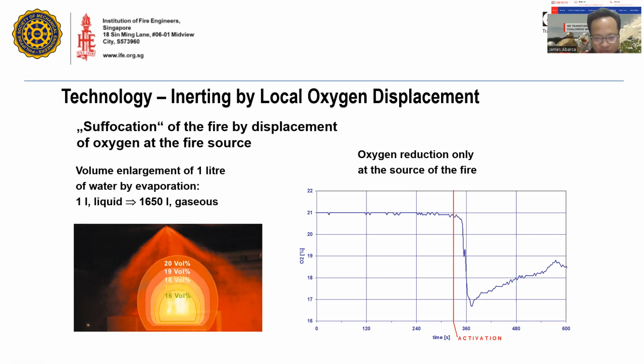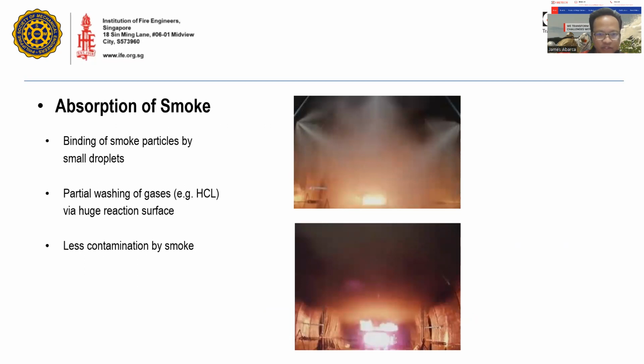Okay, so as we come back to our tetrahedron of fire, you remove the oxygen, you remove the heat, then you are extinguishing the fire. Another good thing about a water mist system is the absorption of smoke. As we all know, when there is a fire, smoke always goes up. And smoke is one of the dangerous byproducts of fire that a person must not be exposed to. Otherwise, he will be suffocated. And when he's suffocated, the tendency is to die.